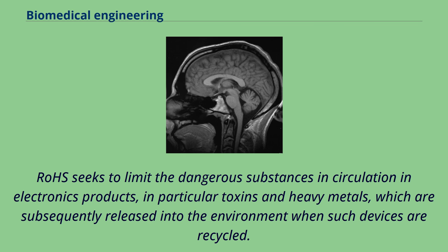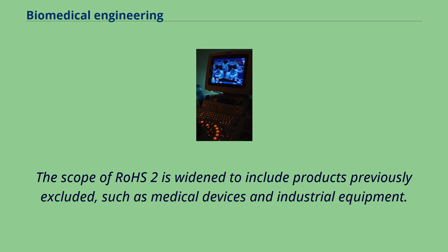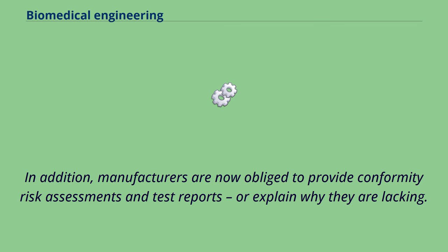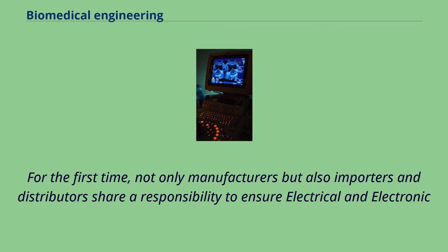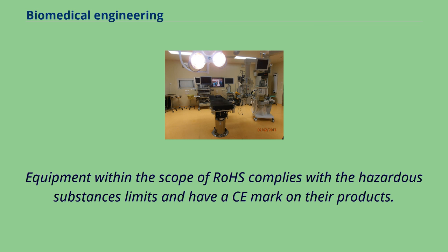The scope of RoHS2 is widened to include products previously excluded, such as medical devices and industrial equipment. Manufacturers are now obliged to provide conformity risk assessments and test reports, or explain why they are lacking. For the first time, not only manufacturers but also importers and distributors share a responsibility to ensure electrical and electronic equipment within the scope of RoHS complies with the hazardous substances limits and have a CE mark on their products.